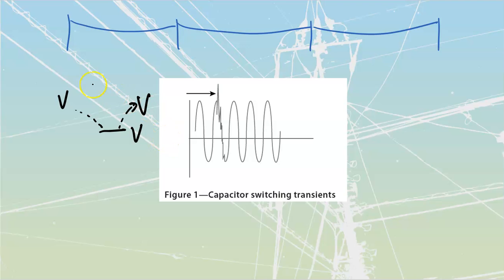Sometimes in industrial areas, during the workday there's a lot more lagging power factor, so they bring the capacitor banks online. But at the end of the day, everybody shuts down and goes home, and suddenly the capacitance would be too high. You don't want overcapacitance, because that increases your transformer terminal voltage, which is bad for all the systems. So they switch those banks on and off.